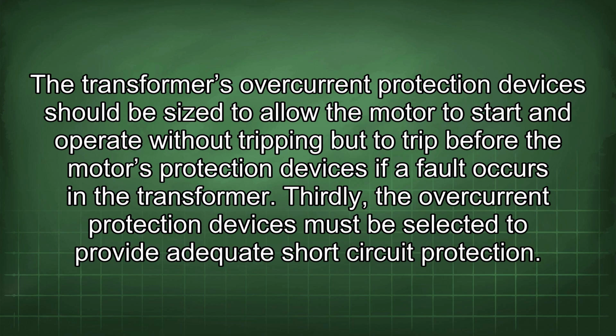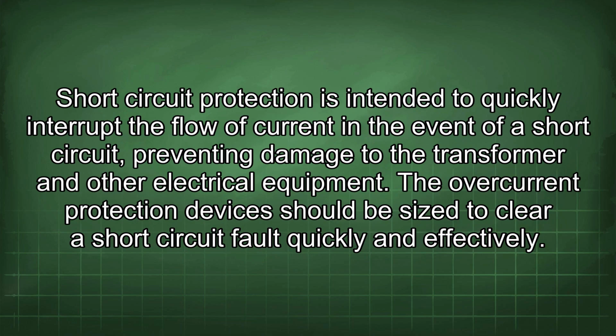Thirdly, the overcurrent protection devices must be selected to provide adequate short-circuit protection. Short-circuit protection is intended to quickly interrupt the flow of current in the event of a short circuit, preventing damage to the transformer and other electrical equipment. The overcurrent protection devices should be sized to clear a short-circuit fault quickly and effectively.